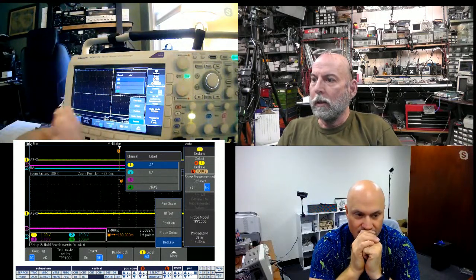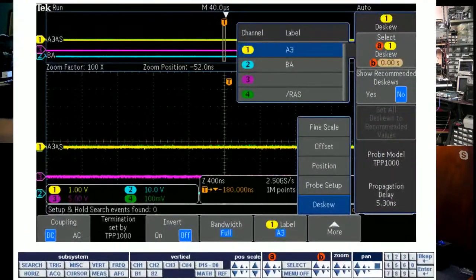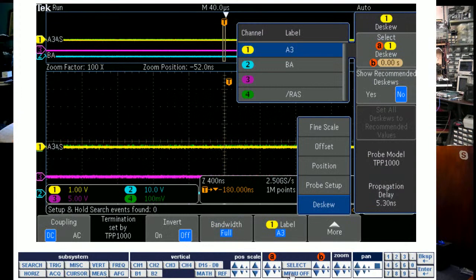channel. So let's say, for example, I had a voltage probe on one of my scope inputs and a current probe on the other input, and I want to use that to measure power, for example, through a device. The voltage probe might have a different propagation delay from probe tip to the scope input than the current probe does. All right, so you may have to apply a skew to them to make them line up in time, especially if you've got voltages and currents that are varying over time.